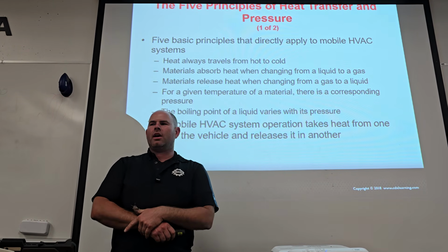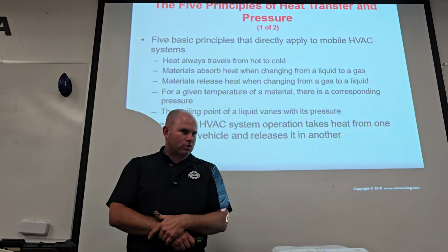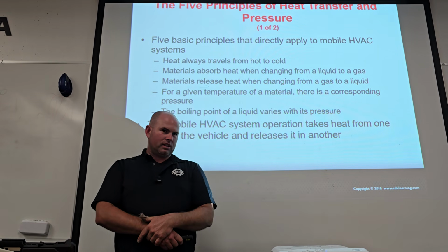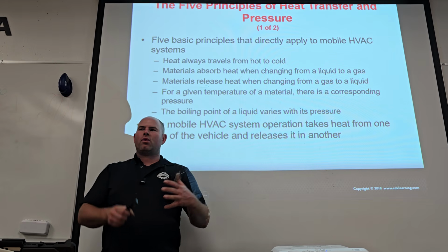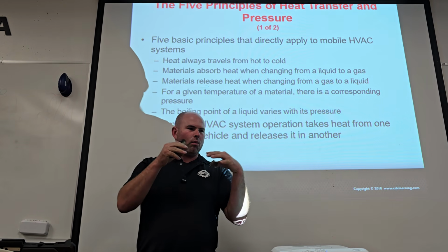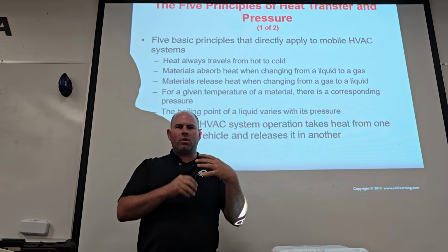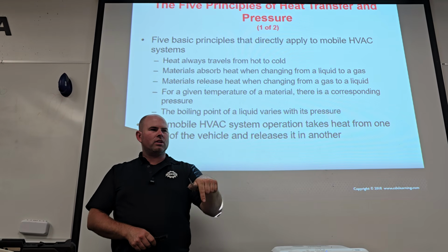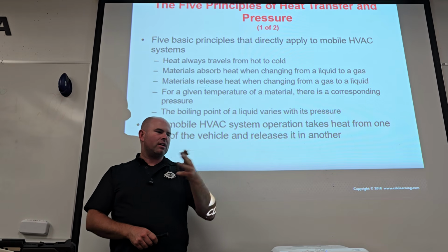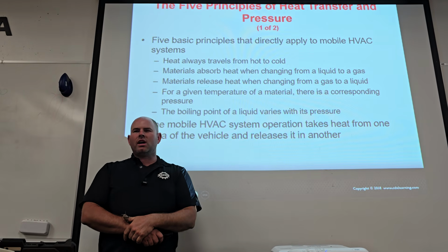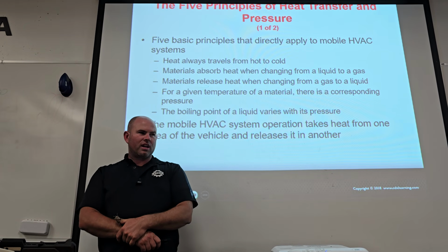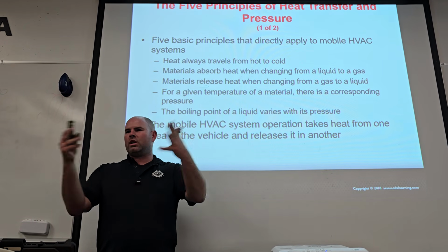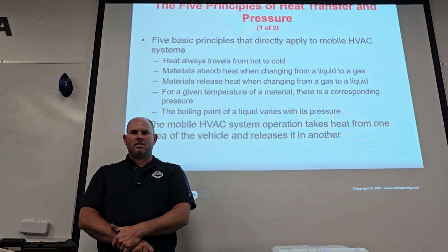That's true at sea level. That's only true at sea level. Did you know if you were to pressurize that water, it wouldn't boil at 212 anymore? For every 1 psi you increase it, it increases the boiling point about 2.5 degrees. All right, you guys know your cars run hotter than 212, right? Why doesn't the coolant boil over? Because it's enclosed or it's capped?